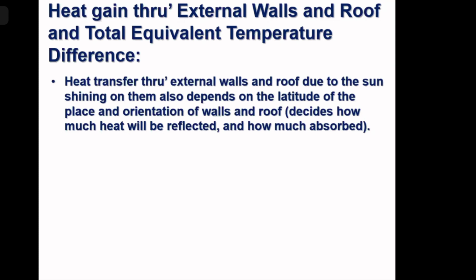It will also depend upon the location's daily range of temperature. Some places' temperature varies quite a lot. Like here where I am now staying, the morning temperature is 10 degrees centigrade and the noon temperature is 24, 25 degrees centigrade. So that is a 14, 15 degrees centigrade temperature variation. But in Calcutta nowadays it may be 5, 6 degrees centigrade. So if the temperature range is more, your building material gets the opportunity to cool down more and then pick up heat again. But if the temperature range is not that big, your building material doesn't get cooled much. So your heat transfer pattern will be different. So instead of that, let us take the total equivalent temperature difference instead of the actual delta T. Next.